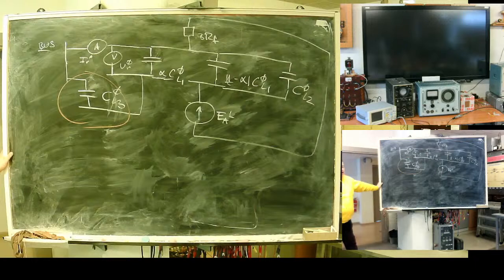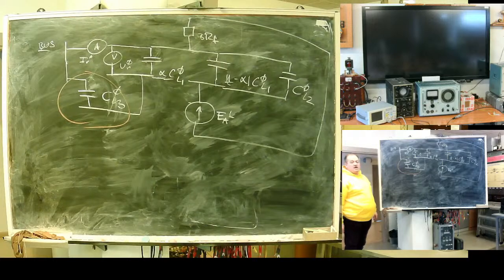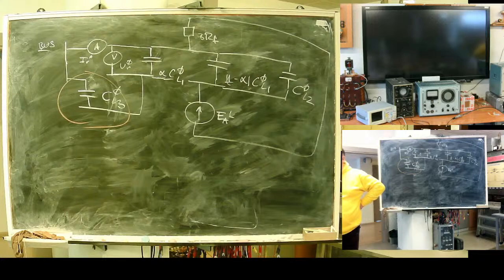You in upside down world. Your current through relay is determined by non-damaged part of the network. Lines what come to your bus outside this part behind your back. That's what sets a current for you. Meaning, typical overcurrent protection approach will not work here. We are in strange position. What will work? In such kind of network, we can only rely on what? Direction.